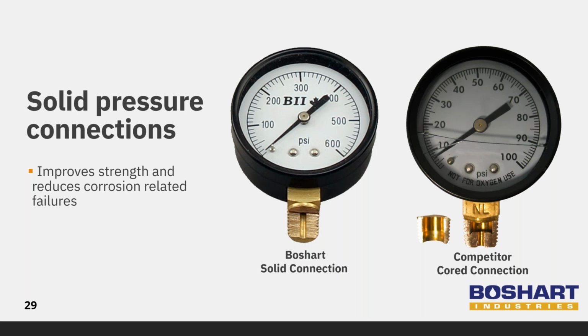On the right-hand side of the slide, you will see a typical competitor's gauge with a cored connection. This extremely thin wall can break when tightening the gauge and is especially prone to breaking when removing the gauge. Oftentimes, a plug is inserted into the cored connection to give the appearance of a solid connection. Corrosion can easily happen between the connection and the inserted plug.